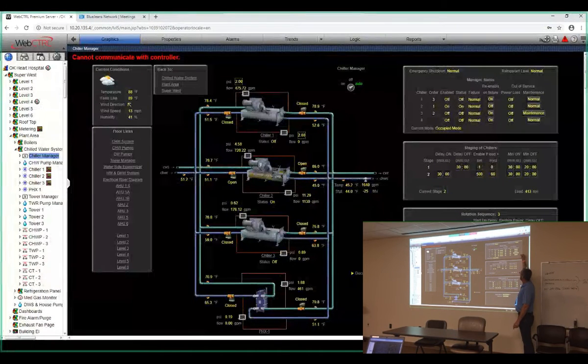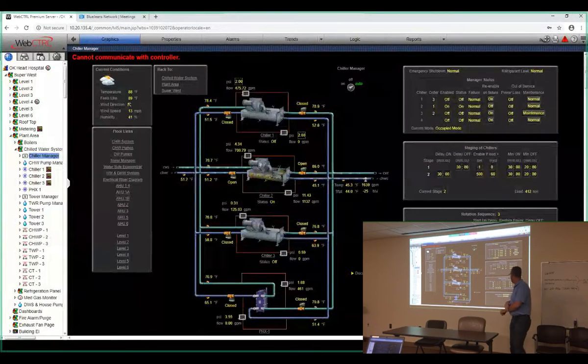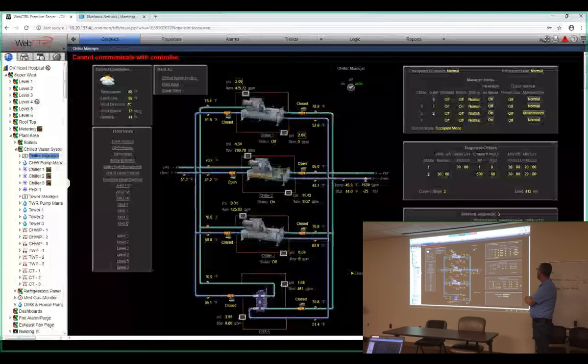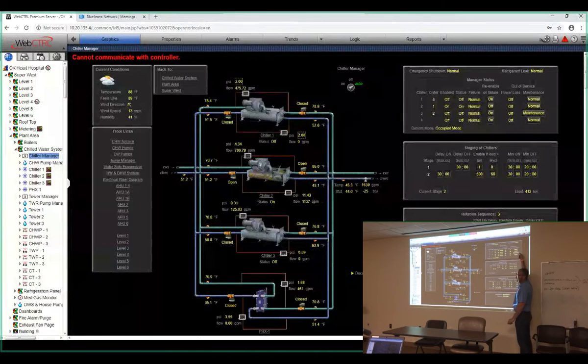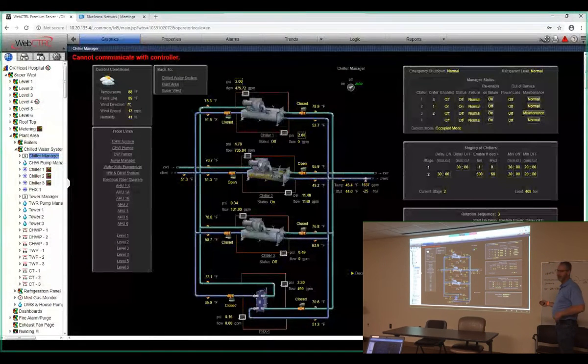Now, if you want to force a unit on, I don't have that on the graphic. I don't have a way to force it on. You could put it in maintenance from here, or you can put it into rotation. Maintenance will lock out a chiller. Here's where I locked out. This is where, if I wanted to lock a chiller on right now, I could turn it on just by clicking that button. That's going to start chiller 1.